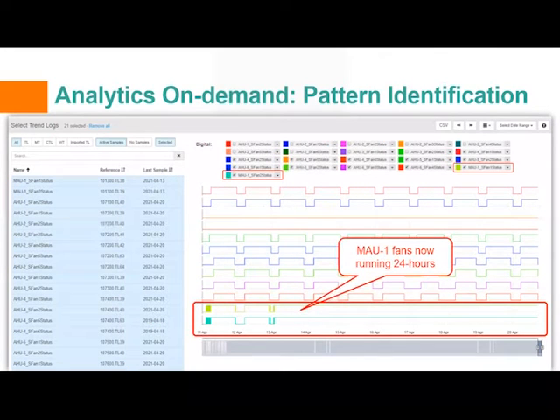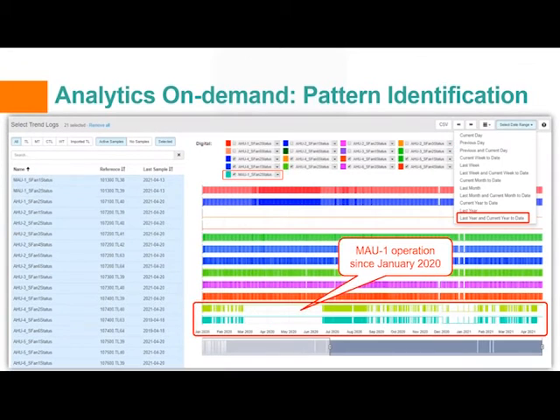With this type of view, finding anomalies or systems deviating from the norm is often an easier process. In this example, we're using the same group of systems from the previous slide. You'll notice when looking through our supply fan status points, we can quickly determine a normal operation pattern and also detect any outliers. In this case, we can see that the two fan status points for MAU1 have both been running from April 13th onwards. This leads to the question, why is MAU1 running when the building isn't occupied? So, can we use analytics to further investigate the continuous operation of MAU1?